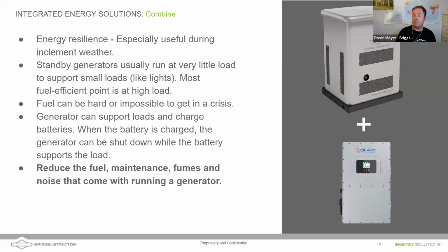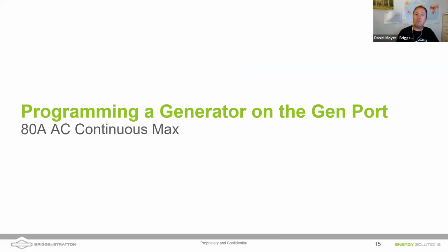So although a generator sometimes can be less expensive up front, when you start to look at the price of propane, which could be $2 or $3 a gallon, and one of these generators might use 2 gallons an hour, that fuel cost starts to add up, along with maintenance on that, and frankly, the noise as well. So always make sure you got the exhaust pointed towards your neighbor's house and not towards your bedroom window as well.